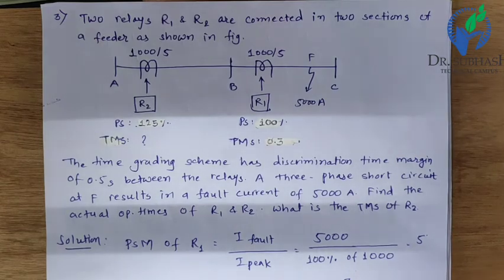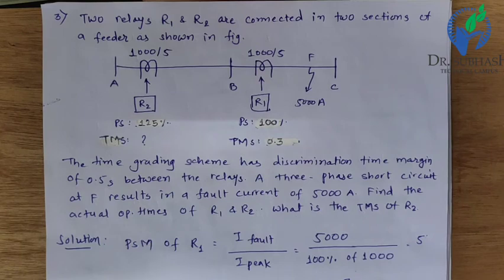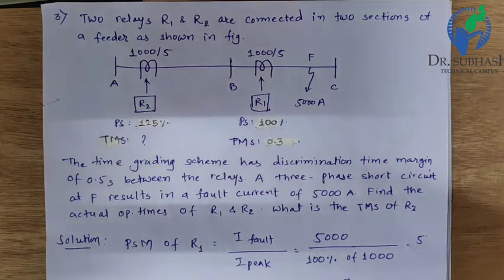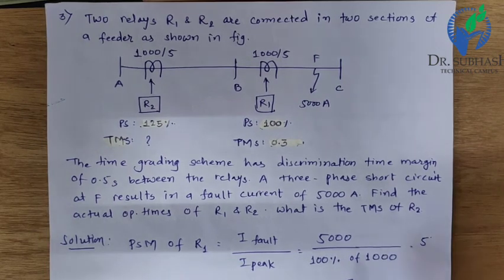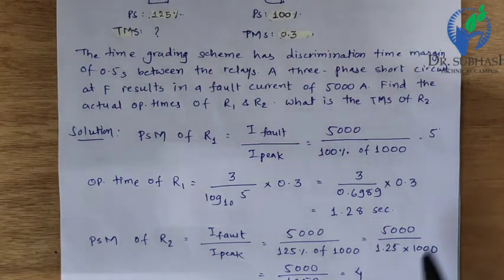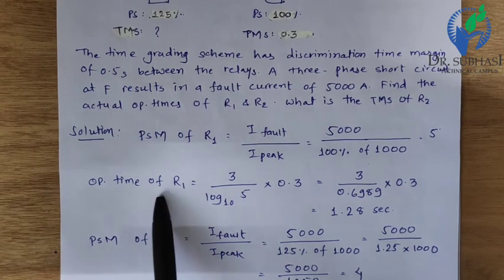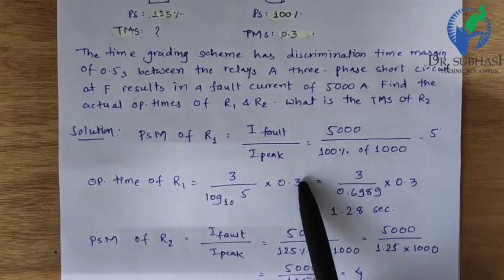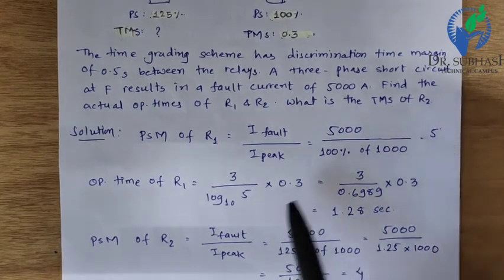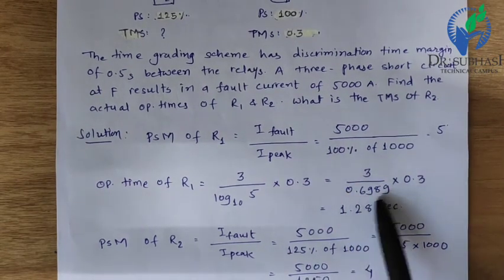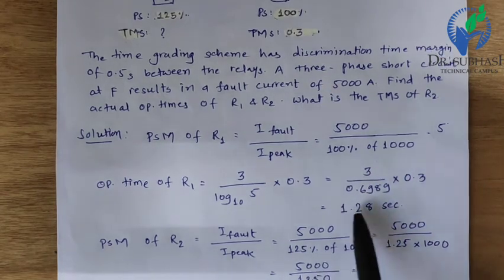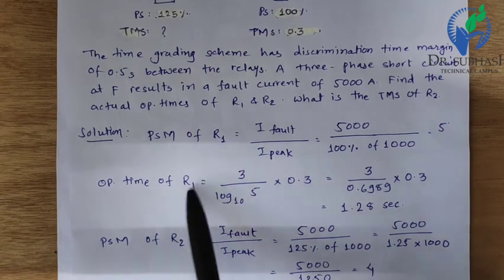For R1: PSM = I_fault / I_pickup = 5000 / (100% × 1000) = 5. Operating time T = 3 / (log10(PSM)) × TMS = 3 / (log10(5)) × 0.3 = 1.28 seconds. This is the operating time of R1.